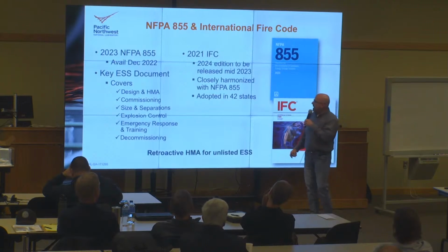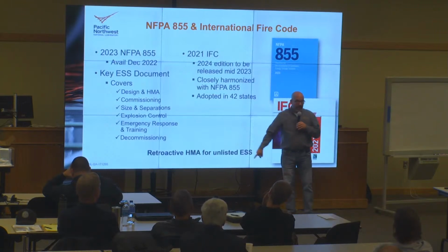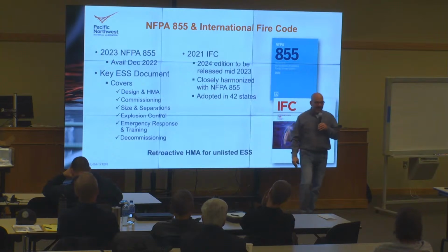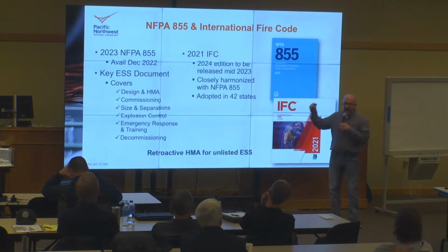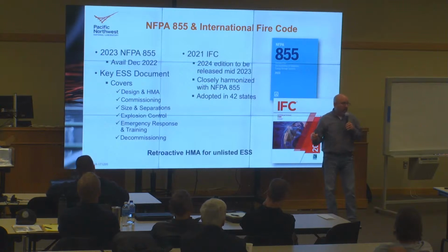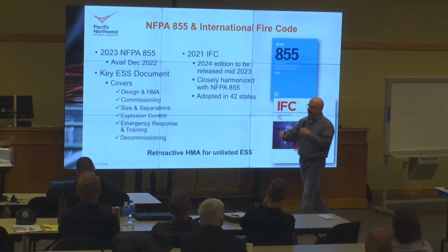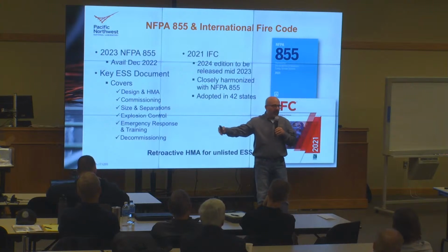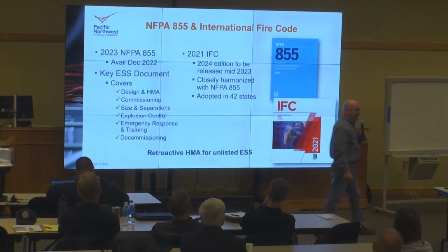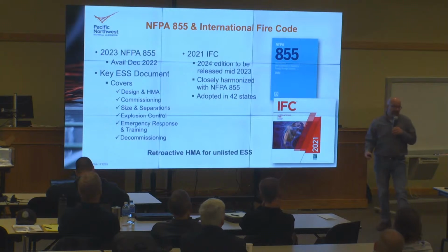And anyways, this line down here is a really key one - I'm sorry for putting it at the bottom of the slide. In both 855 and the 2024 IFC, there's a requirement for an HMA, hazard mitigation analysis, on unlisted existing systems. So it gives the AHJ the ability to go and say, hey, that system installed 5 years ago, let's see what the risks are and come up with a report. That's going to be problematic for some of these older systems, because what they're going to find is the explosion risk wasn't addressed, and doing that retrofit is going to be really hard.